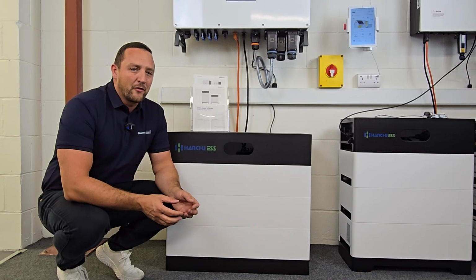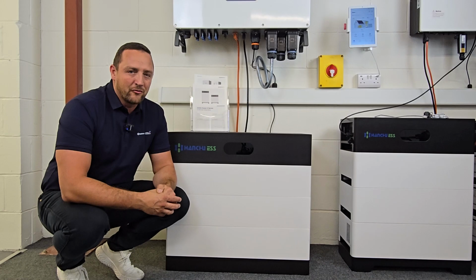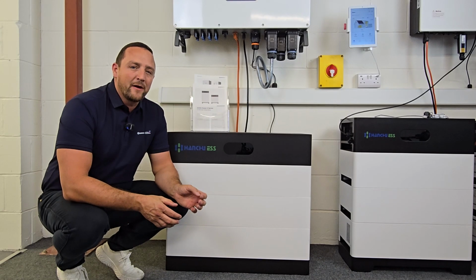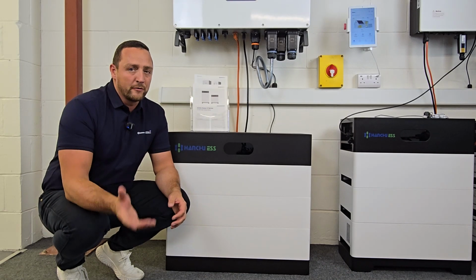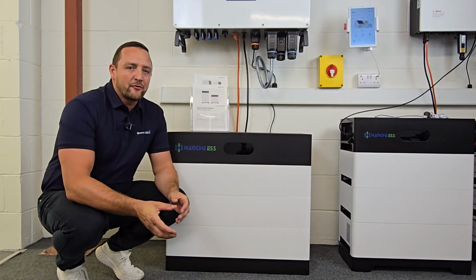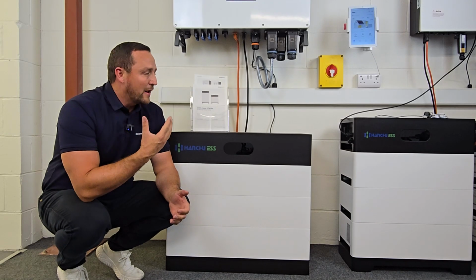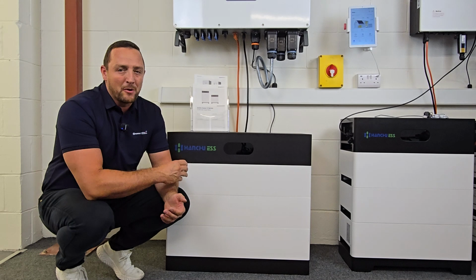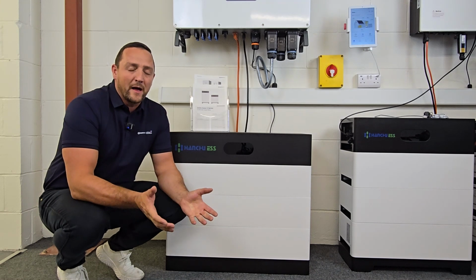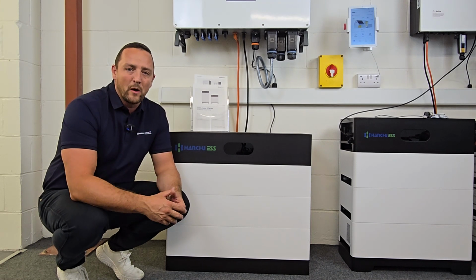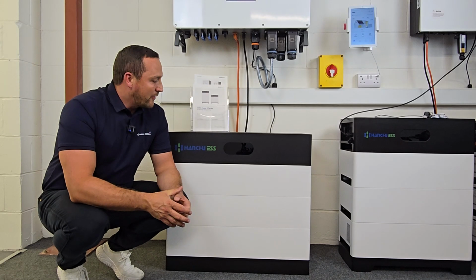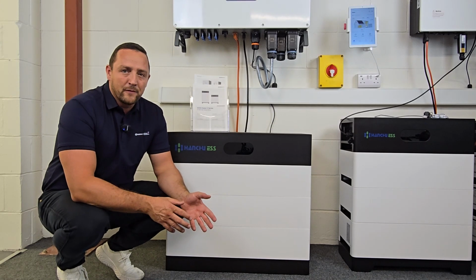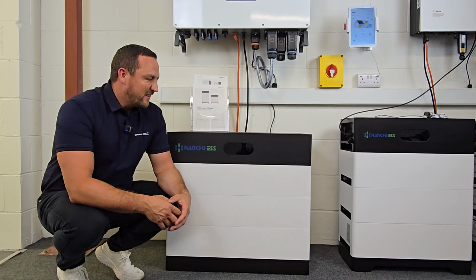With these batteries, they are a 95% depth of discharge. You get almost full capacity out of every battery, maximizing the return on investment. Each battery is individually monitored as well, just like the controller. We can now monitor each individual battery through the AI platform, that's app and web portal. And we can take a real good look at the health, the state of the batteries, and basically what's going on throughout the system.